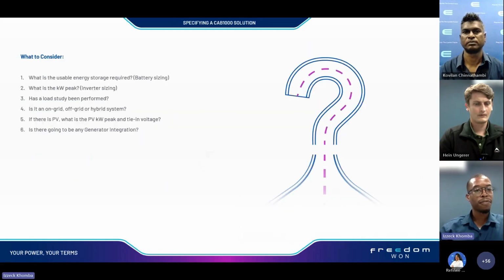Then looking at some of the considerations when speccing the system, what you need to understand is your usable energy storage required, which will basically influence your battery sizing. Then you also need to understand your peak load. Your peak load will help in terms of sizing the inverter correctly. This goes hand in hand with the load study performed. The load study helps in understanding the characteristics of the load and ensuring that the system is designed effectively and will be able to meet the client requirements and function seamlessly.